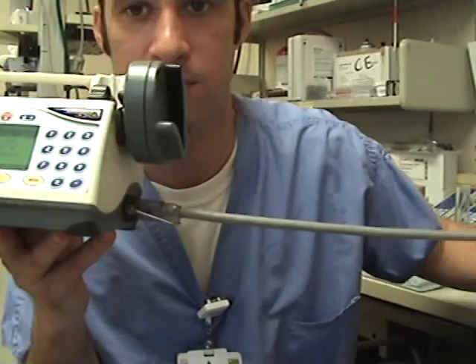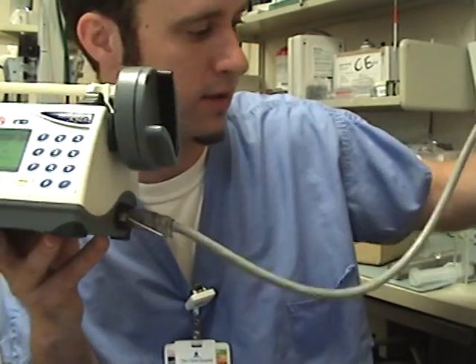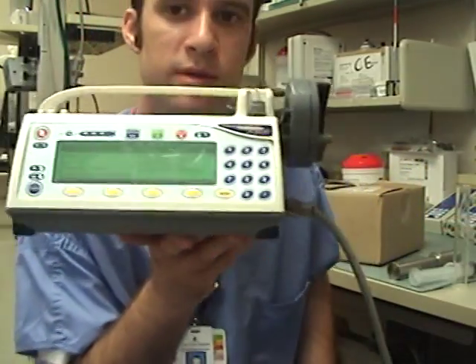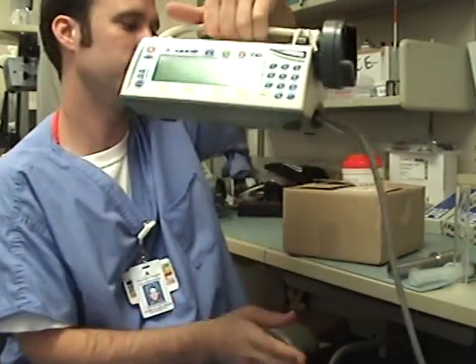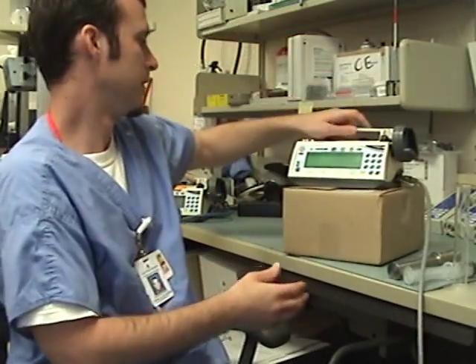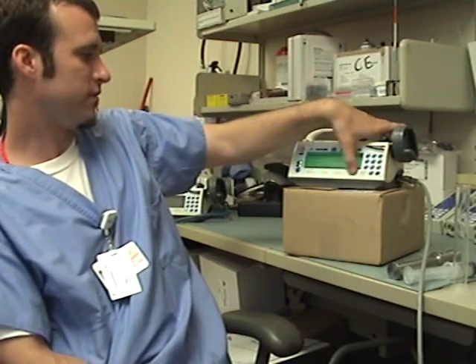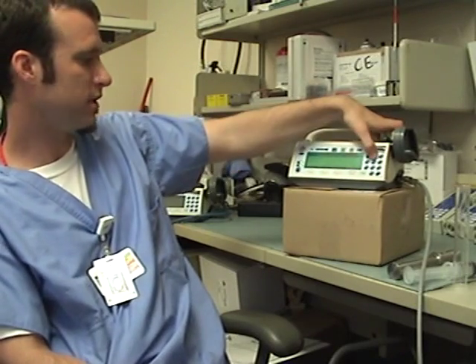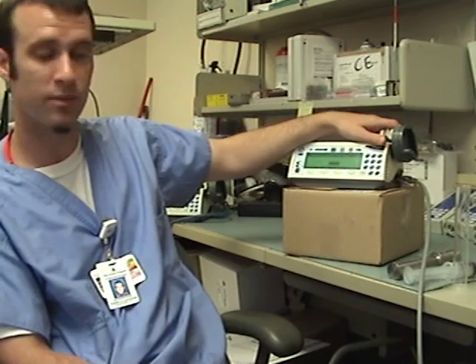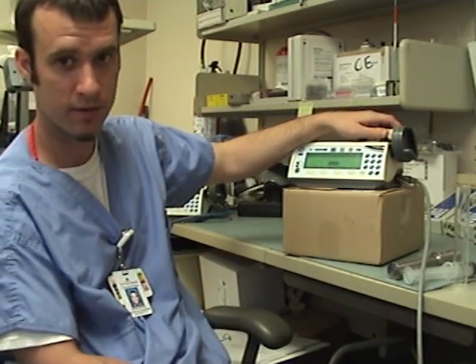Test the power cord, make sure that there's no frays, breaks, kinks in the line. These units are double insulated, so they do not need to be electrical safety tested. Once you enter into the device, on the second settings screen there's a BMET mode. Once you get into the BMET mode, you're going to need to put in the lockout code, which is based per facility.